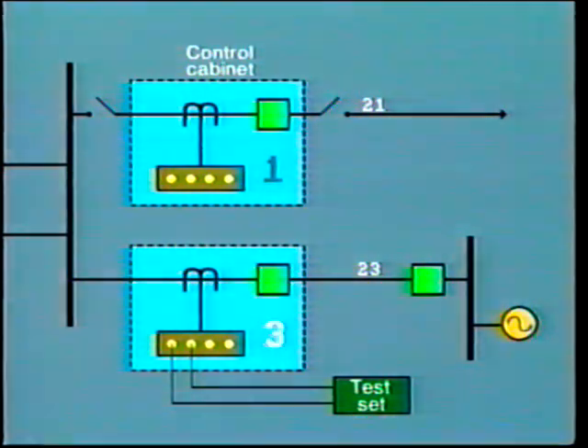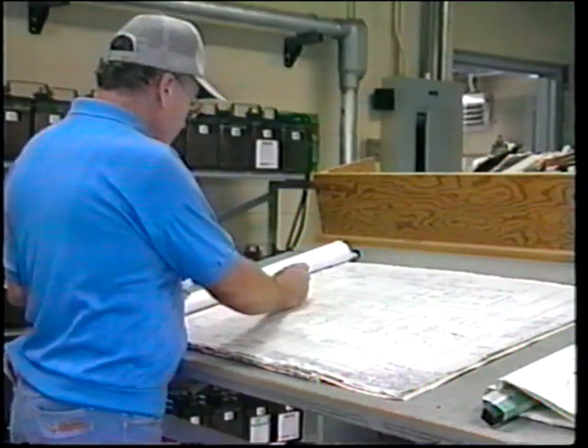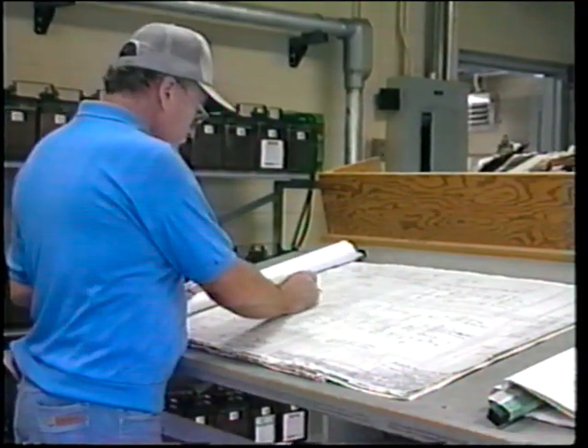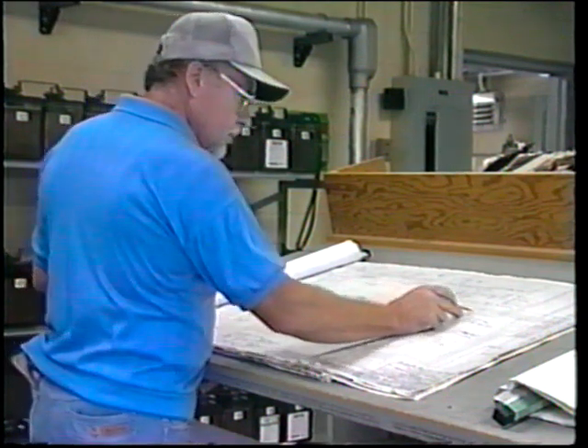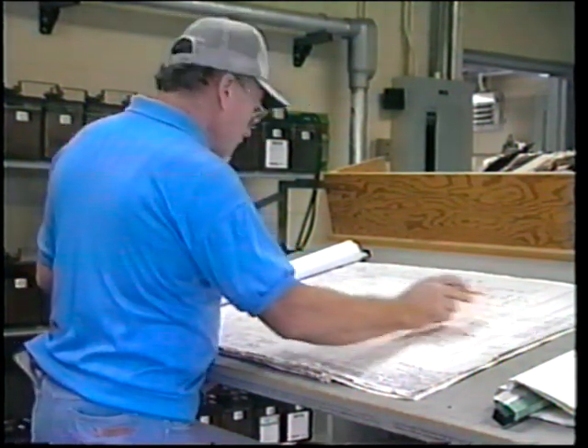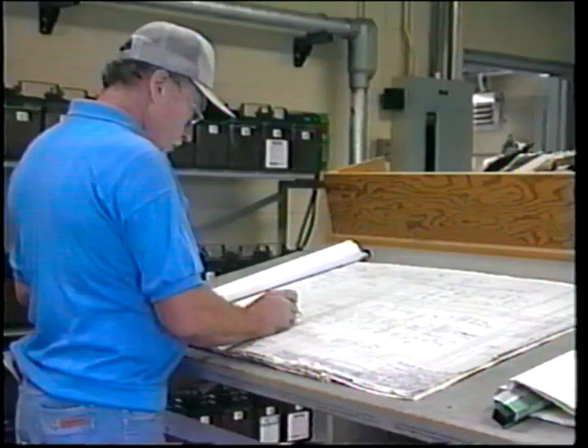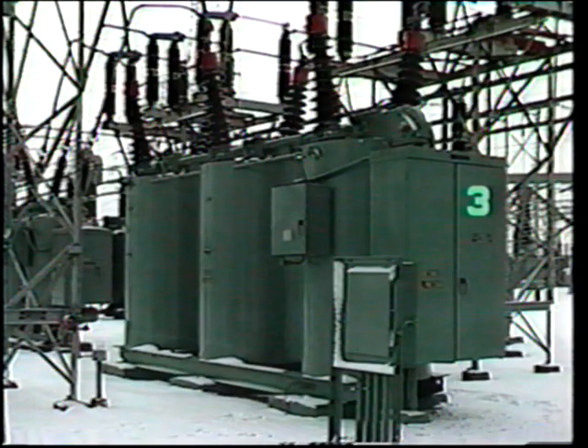The breaker panel was clearly marked number 3, but the technicians had been misled by using a schematic diagram which showed the number 1 panel to be located close to the relay house. Here, then, is the nub of the problem. First, they should have been utilizing the physical wiring diagrams which actually show the true geographic layout. Also, all of us must always check the identification of any equipment on which we intend to work.